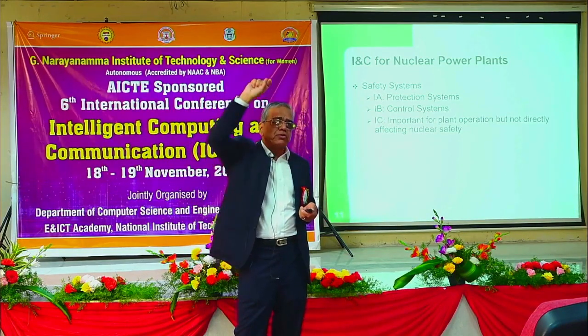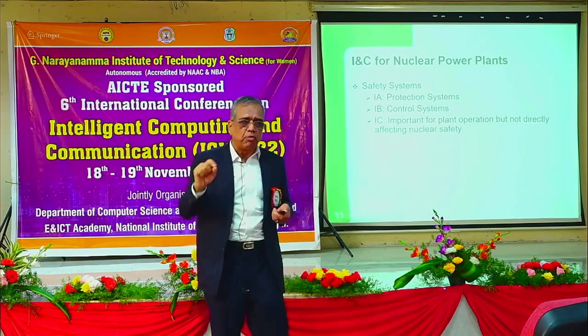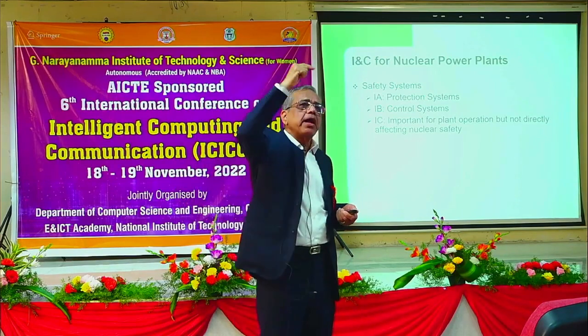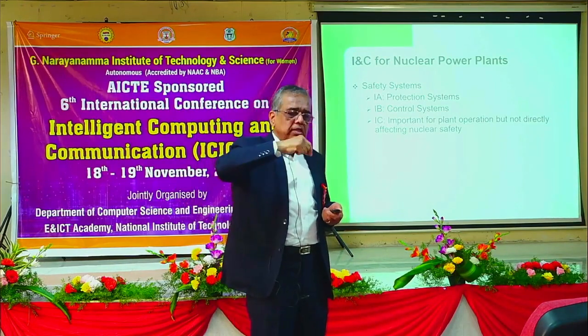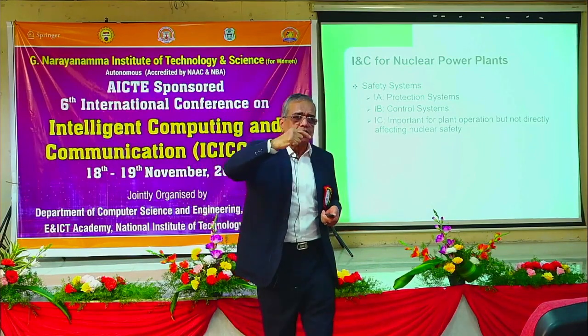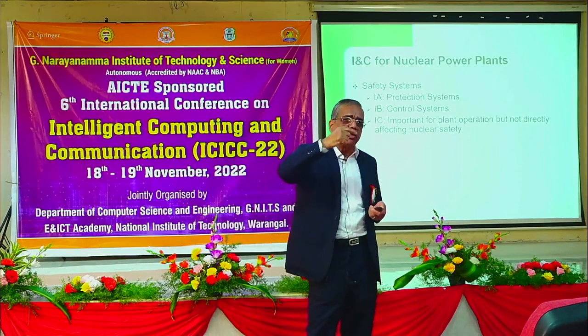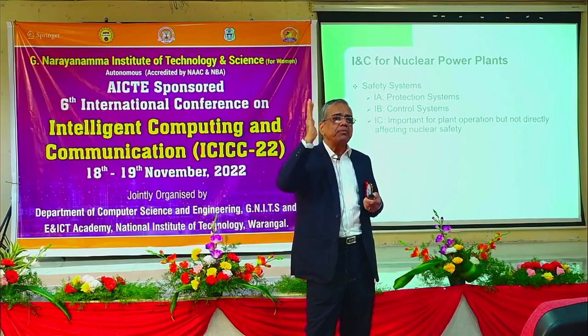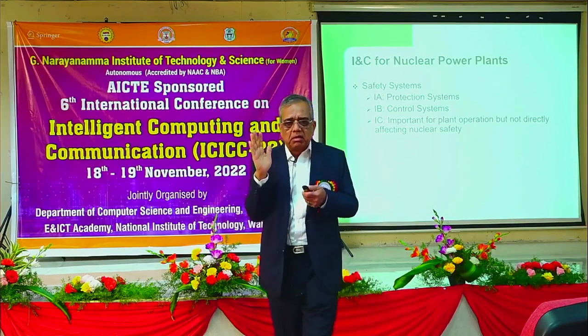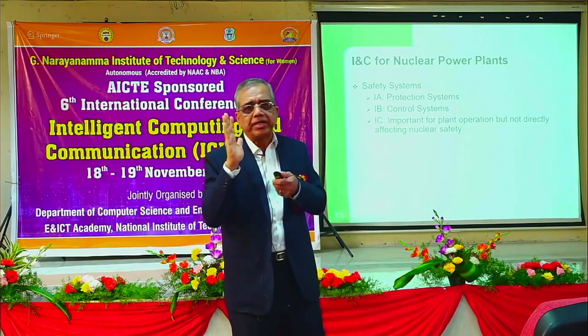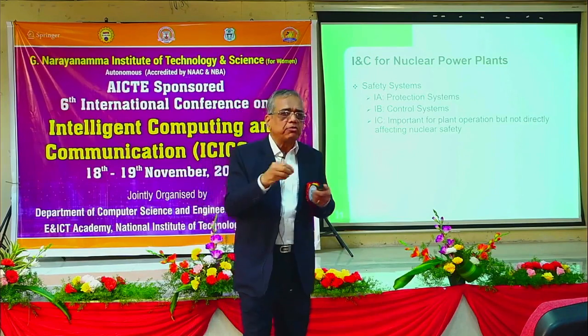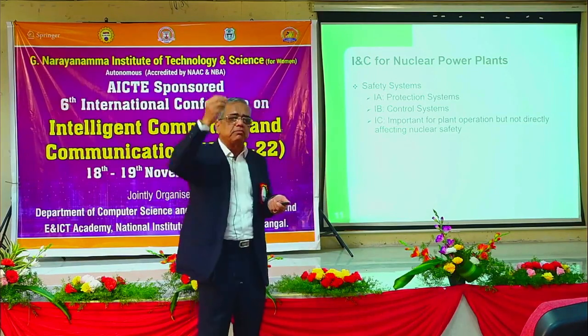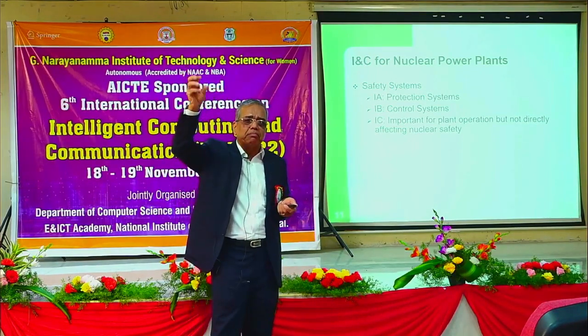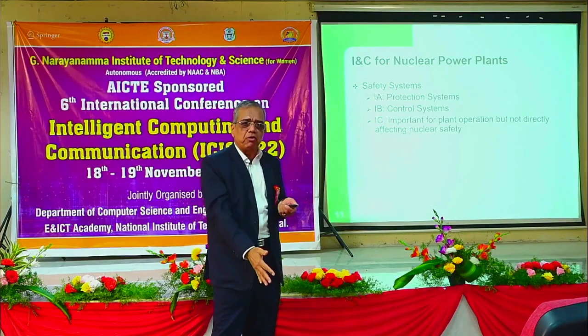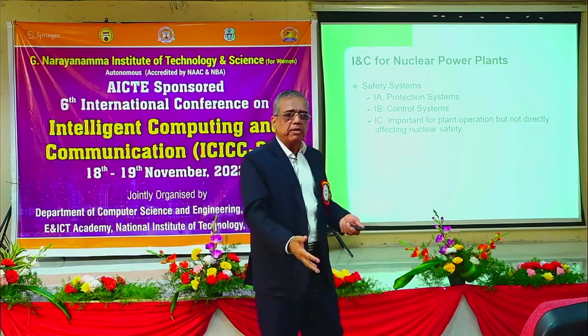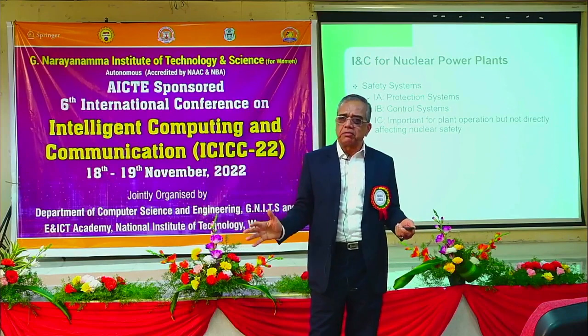These shutdown rods consist of neutron-absorbing material rods, such as boron carbide. They are hung by a steel rope, which is wound on a drum, and the drum is held in place by a magnetic clutch. If something happens, the protection system will de-energize the clutch, the power supply will disconnect, and the rods will fall by gravity, absorbing all the neutrons so the reactor shuts down.